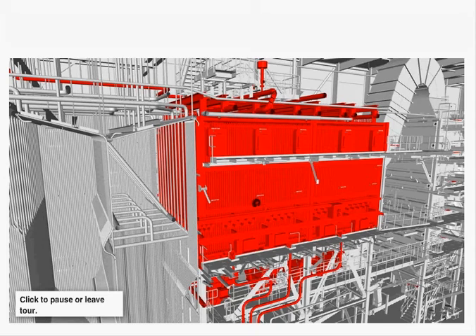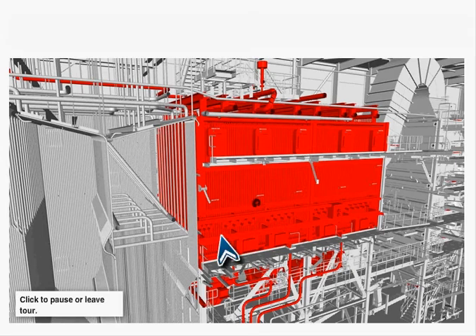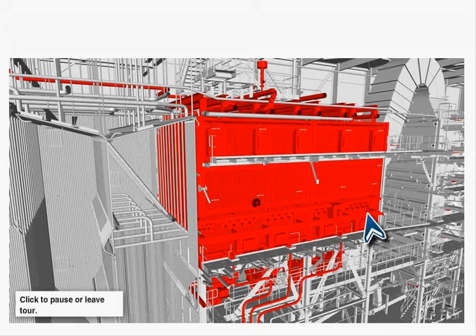After leaving the turbine, the steam goes to an air-cooled condenser and will return to the boiler as feed water. The superheater section is cleaned by pneumatic rapping devices. In order to avoid corrosion in the final superheater section, we've developed a special configuration of the bundles. It's just one of the many innovations resulting from our years of experience.